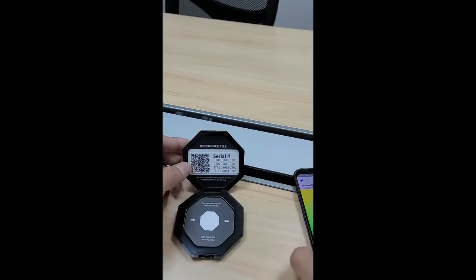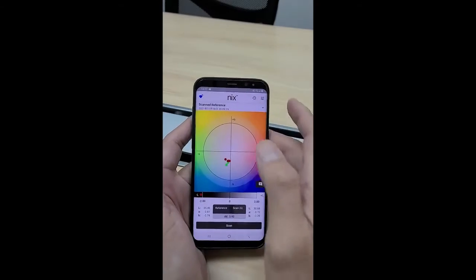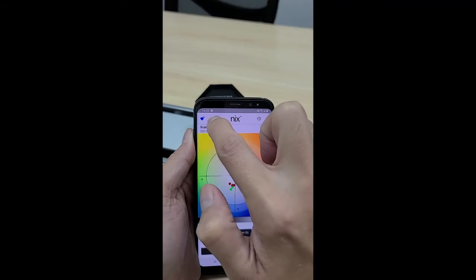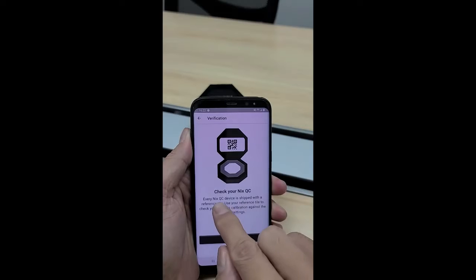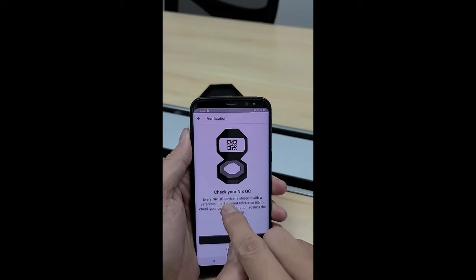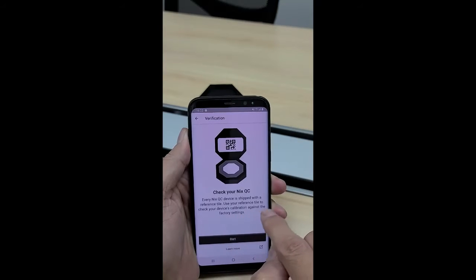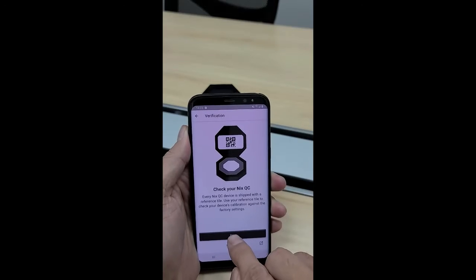Open the tile and tap this icon. You will see a message: 'Check your Nix QC — the Nix QC device is shipped with a reference tile. Use your reference tile to check your device calibration against the factory setting.' Press the Start button.